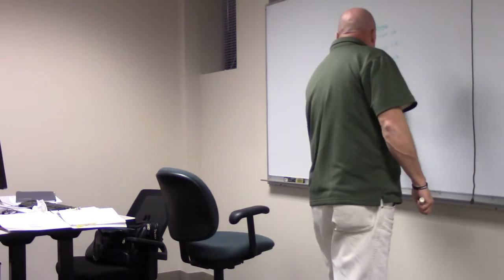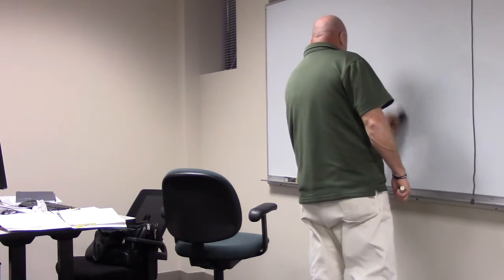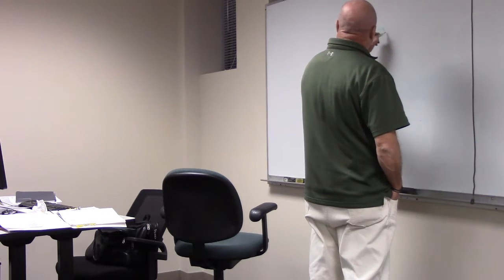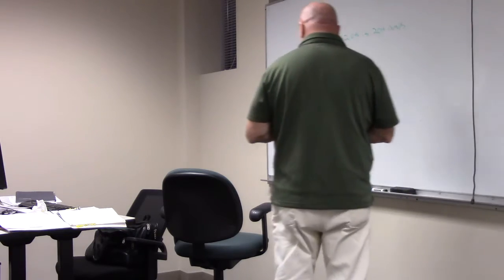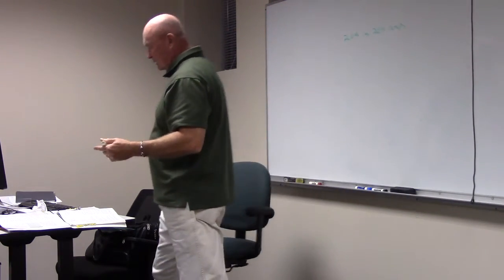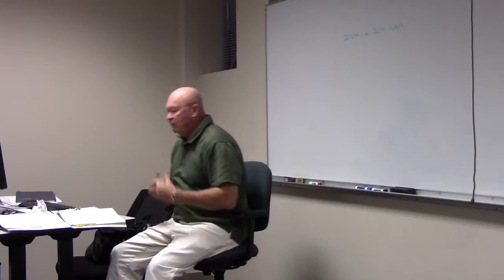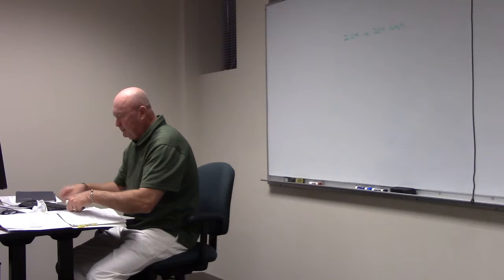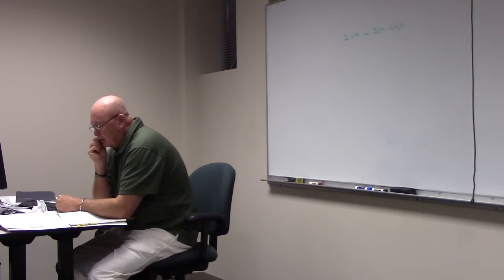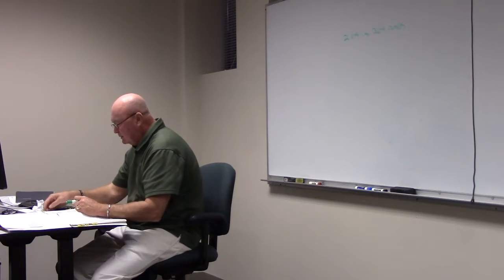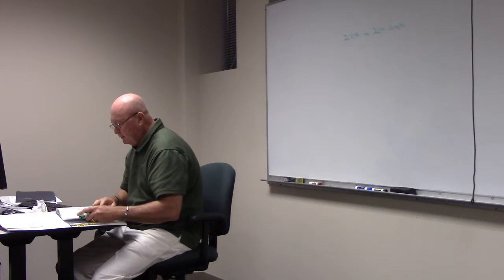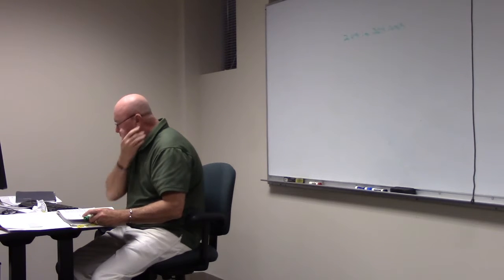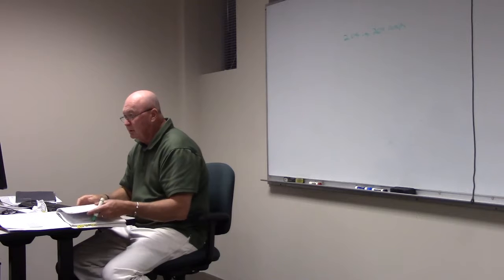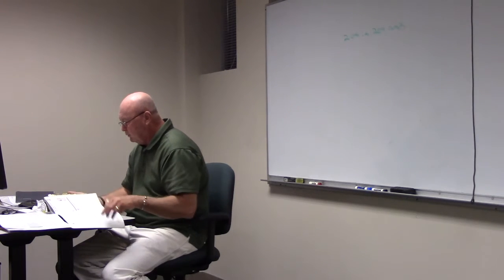Yes. Okay. So our 208, we're going to erase all this now, I don't think we need it anymore. Except we're going to remember one thing. Our 208 is 204 amps? Yes. We may need that. But that's our 208. Now we have to look at step number 10, and it refers us to 480. Well, it talks about the wire. So we're going to go to 310.15(B)(16), and go ahead and size this wire for this 208. Okay. Well, first of all, we'd have to find out what size breaker we'd use. We're going to go to 240.6?